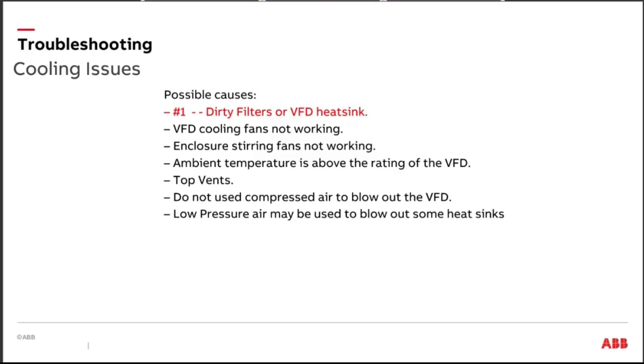I might even take and run, or not might, most of the time, I'll take and put my hand up on the front of that drive enclosure and just try to notice what the fan is, try to notice what the temperature of the enclosure is about. All of our drives enclosures are rated for 40 degrees C. Your body temperature is about 96. Okay, so you should be able to feel real easy with your hand if you've got a heating issue there. Okay. And I'll run my hand across the front.